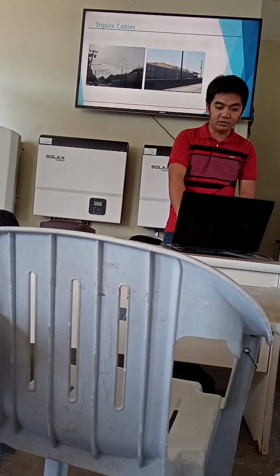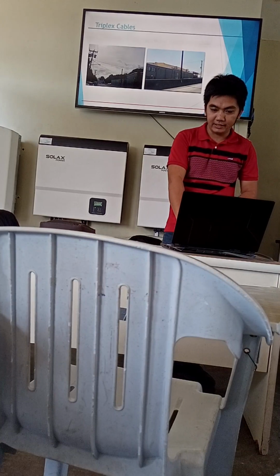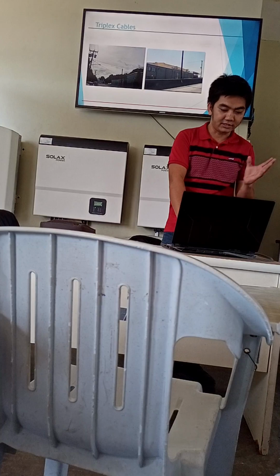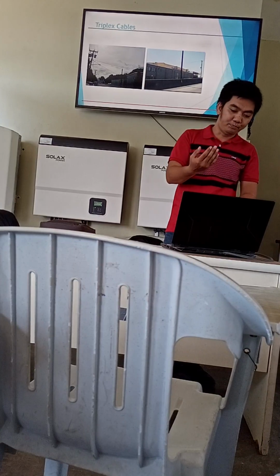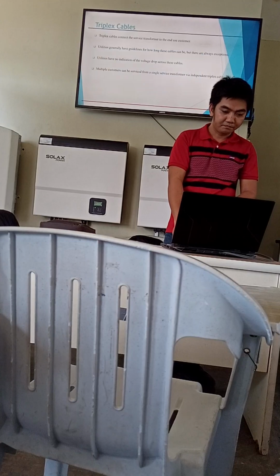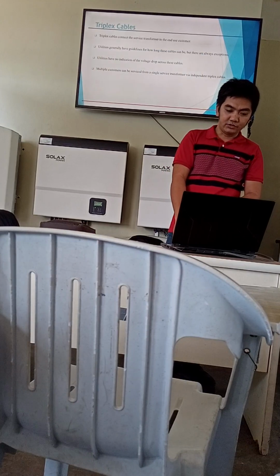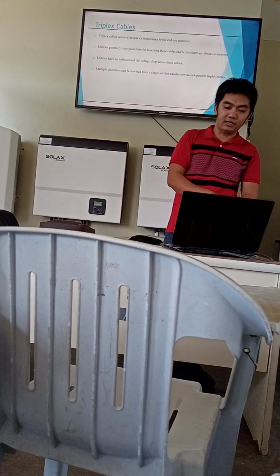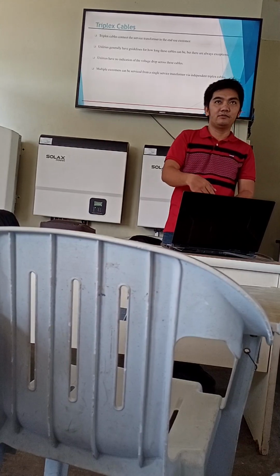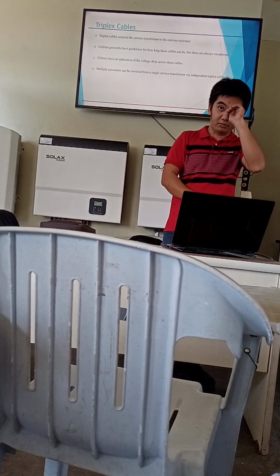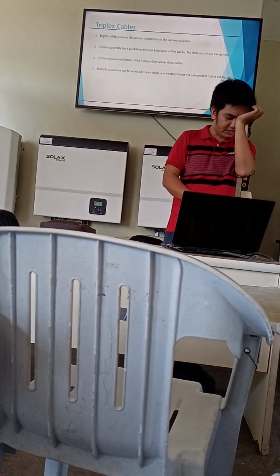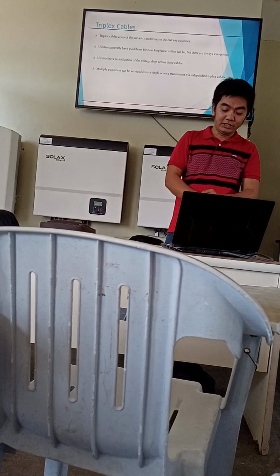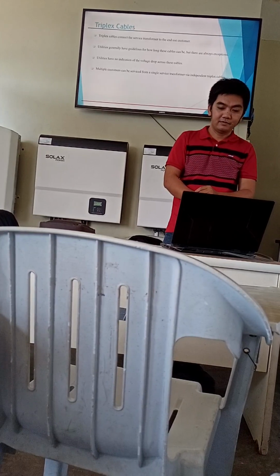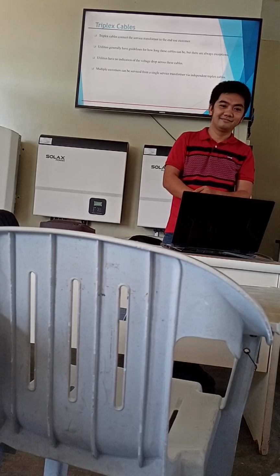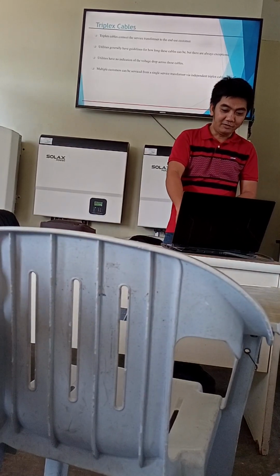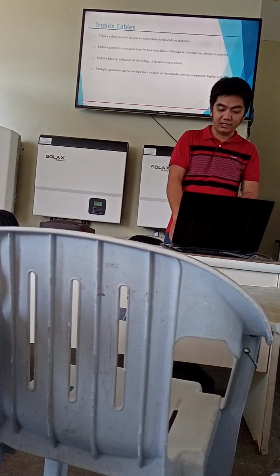Then the triplex cable, which we call the service drop or service entrance, runs from the pole connection to the customer, so to the end consumers. Utilities generally have guidelines on how long this cable can be. In this utility, the limit is 50 meters from the last pole connection. Beyond that, you have to construct another pole. The limit in the distribution code is 50 meters.